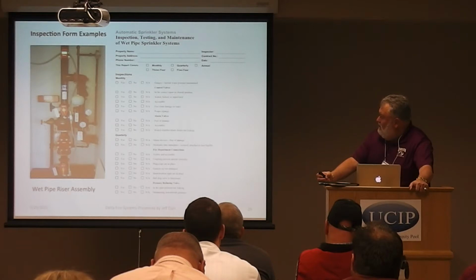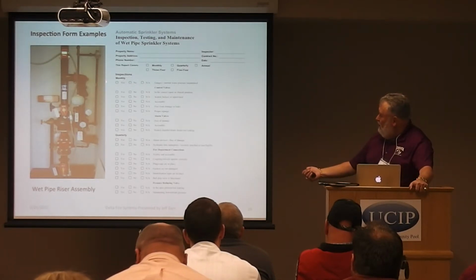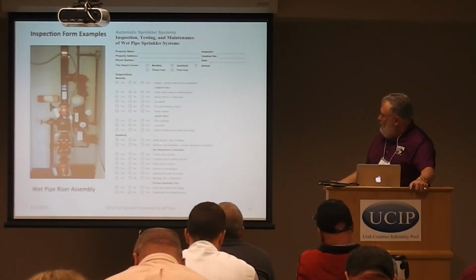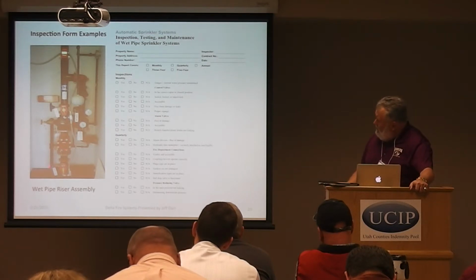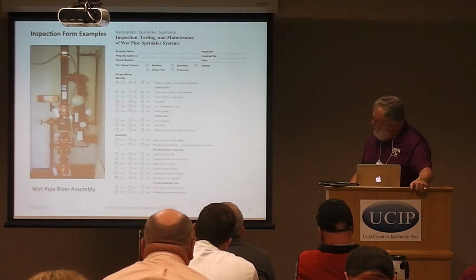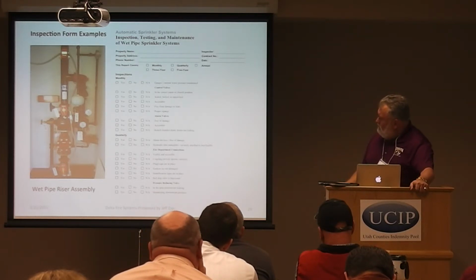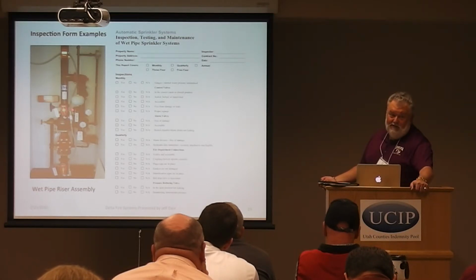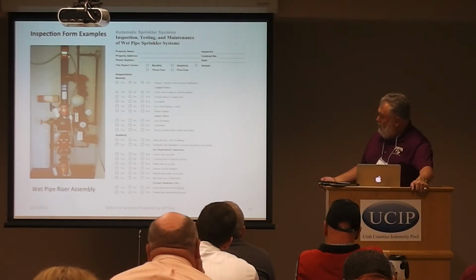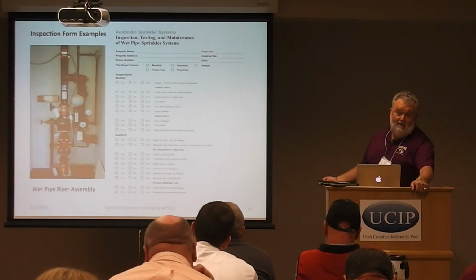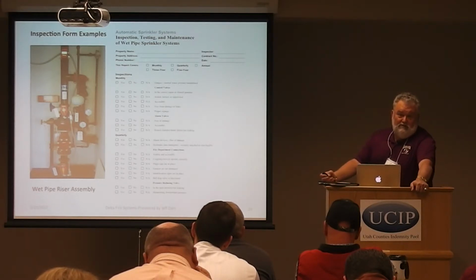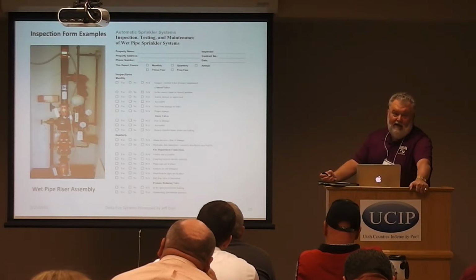Here's an example of a standard wet system. Again, this is breaking it into monthly and quarterly inspections: the fire department connection, the control valve, the alarm valve. On this riser assembly, here are the control valves, one above and one below. That yellow indicator is a visual indicator that you can tell just by looking at it that the system's on, because it is parallel with the pipe. If that yellow indicator was perpendicular, it would tell you that the paddle inside is shut. All sprinkler systems have indicating valves, and they can't close any faster than 5 seconds. The reason is they want you to avoid water hammer on a system. It's not like a standard culinary system where water is usually flowing all the time. These systems are usually stagnant.